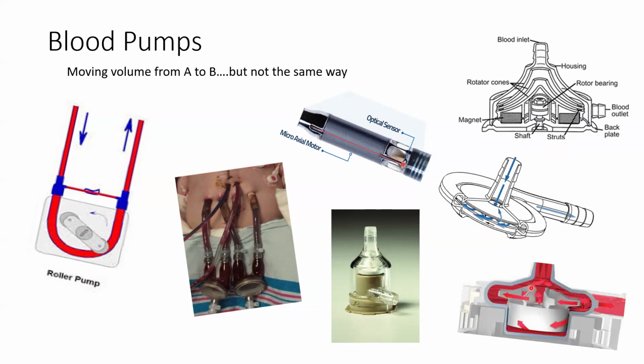The spin of a centrifugal pump applies negative pressure. That negative pressure pulls the blood down into the system, and also that centrifugal force gives high outlet pressures that send blood out to the system.